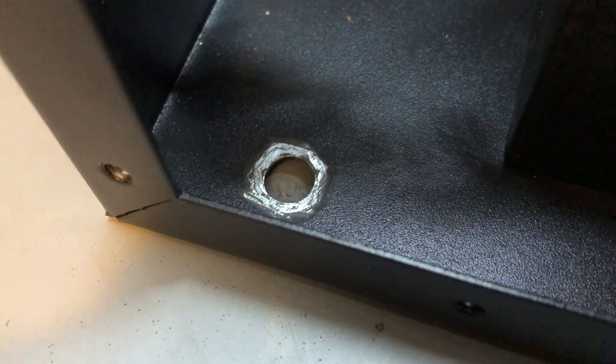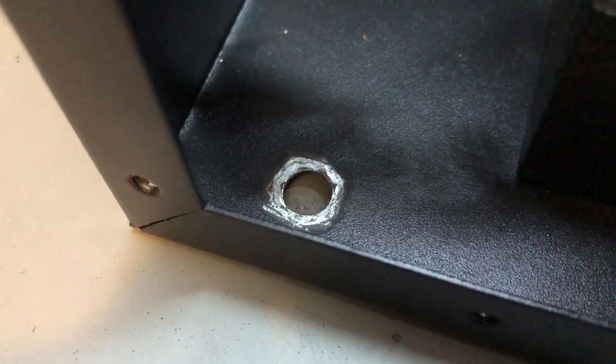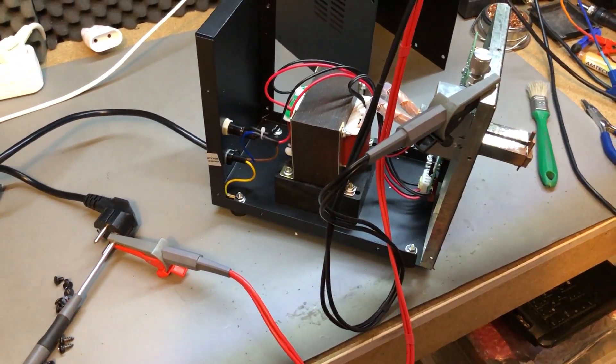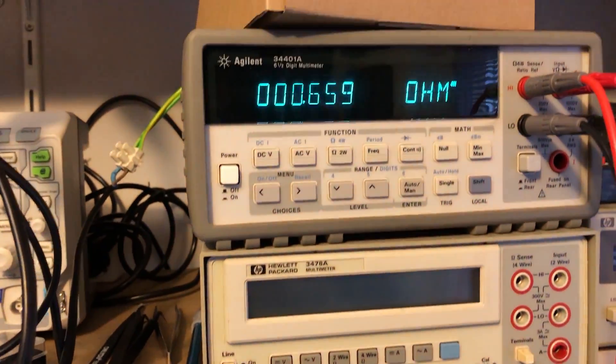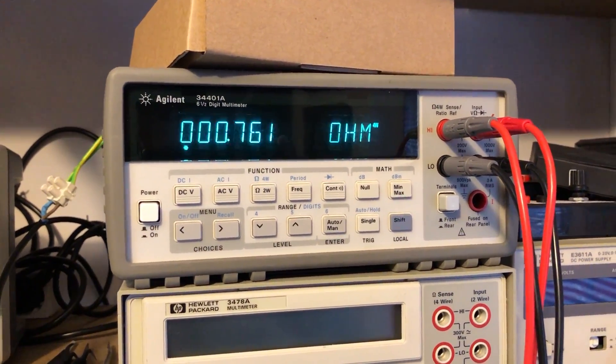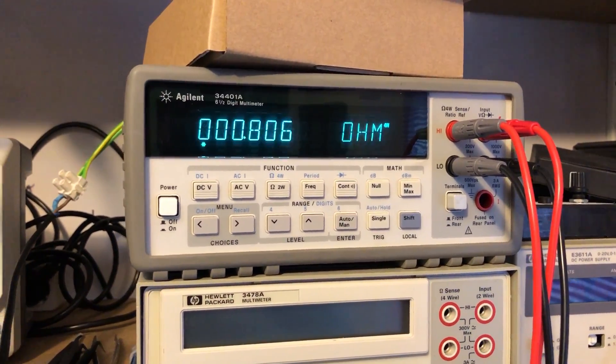Nonetheless, I decided to clean that grounding point. I used a dremel to remove the paint around that screw and after fitting everything back together, I was measuring 0.8 ohms which is an okay value.